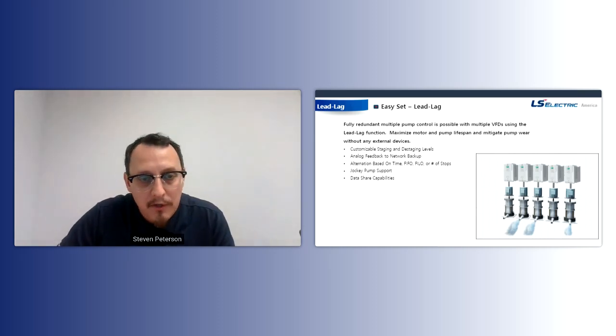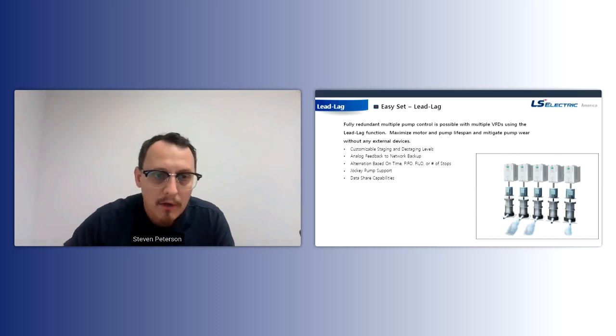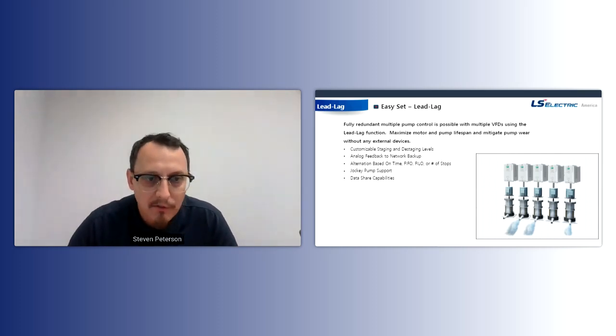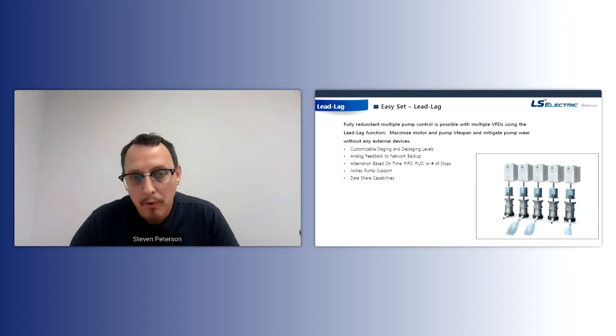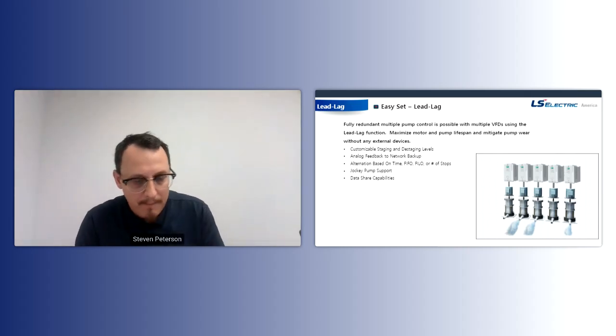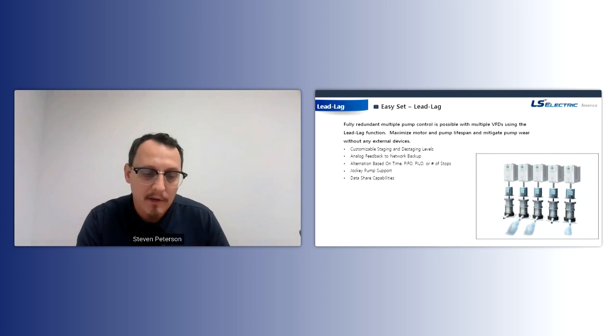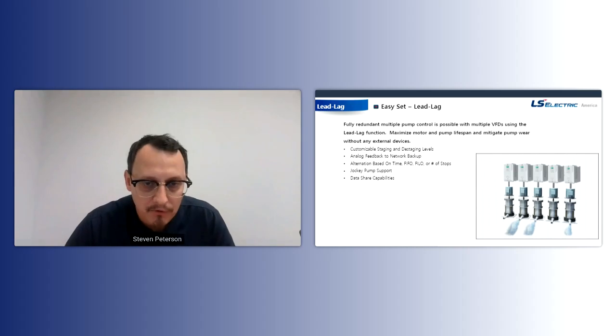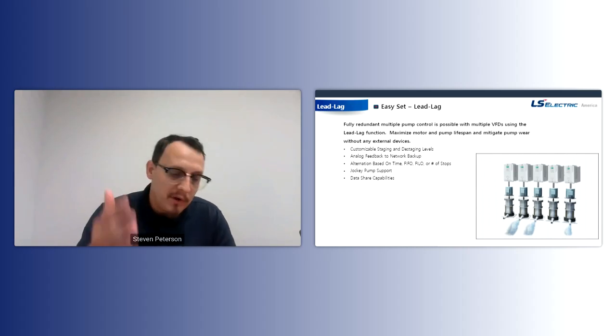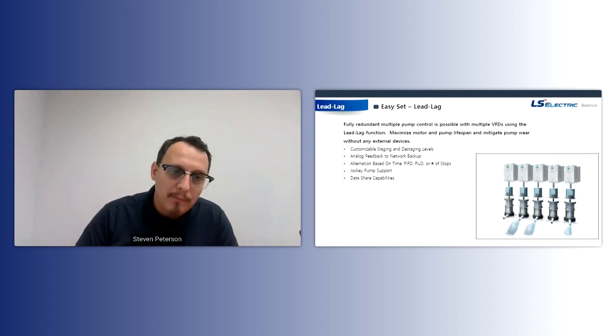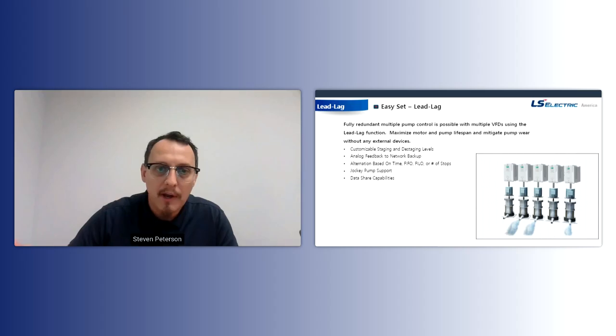Additionally, we can do data share capabilities. One thing that is, is displaying a network feedback device on all the VFDs as possible. And then also you can program one VFD, and that's going to share the parameter set with the other drives. So if you have a triplex of 3 drives, if you program the master drive, as long as you're doing it within the macro, most of those parameters are going to be shared into the other drives. So you don't need to set up the thing 3 times.